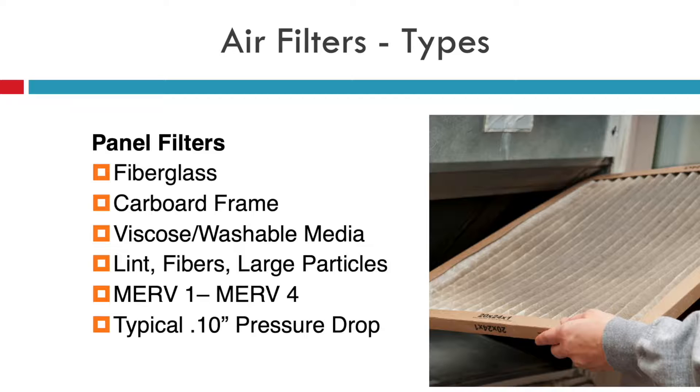The first option, which is usually shipped with most air handlers and furnaces, is just a panel filter. Typically these filters are made out of fiberglass, maybe some MERV 1 or 2 media. They have very little pleats, usually come in a cardboard frame or are washable media, and they're really there to pick up things like lint, fibers, or large particles — stuff you don't want getting in the coil. The minimum efficiency rating value of these filters is somewhere in the MERV 1 to 4 range, with a typical 0.1 inch of pressure drop.